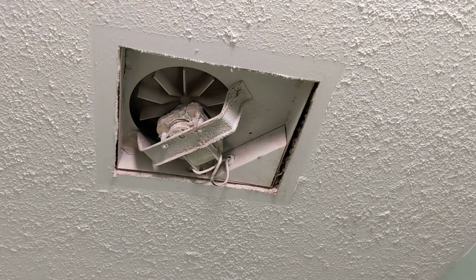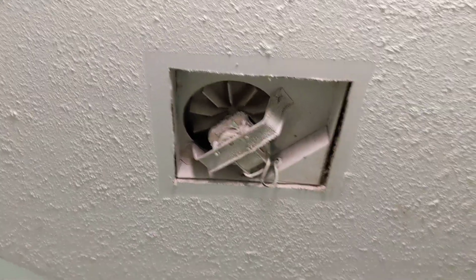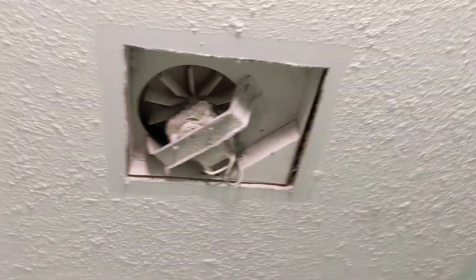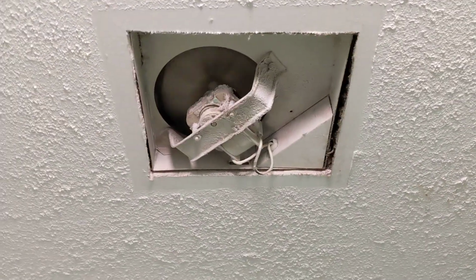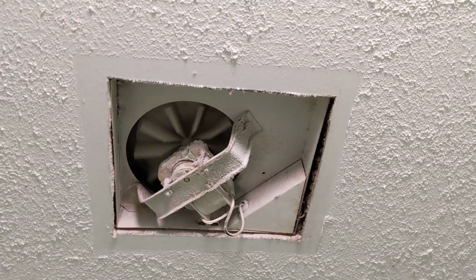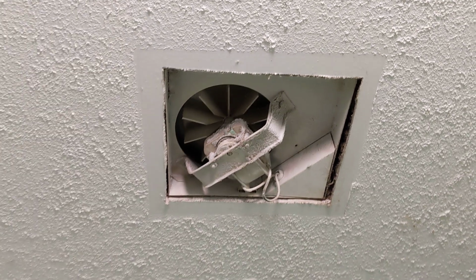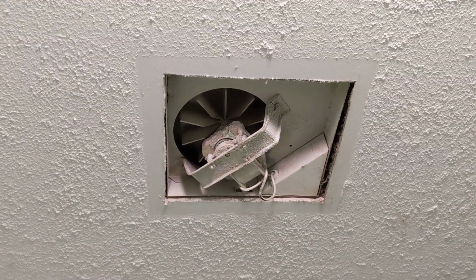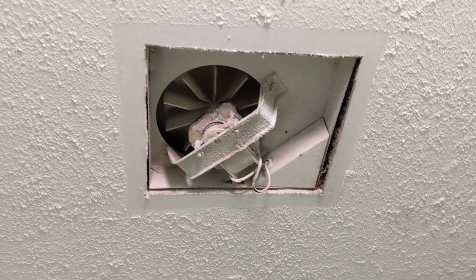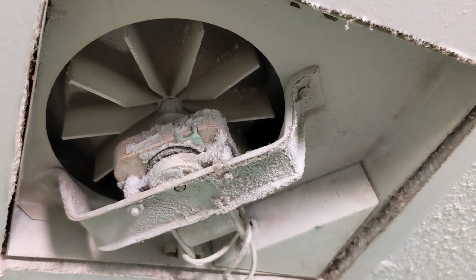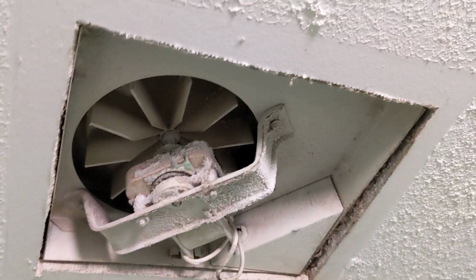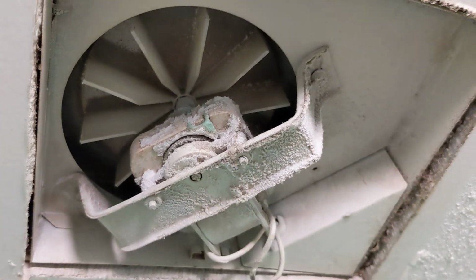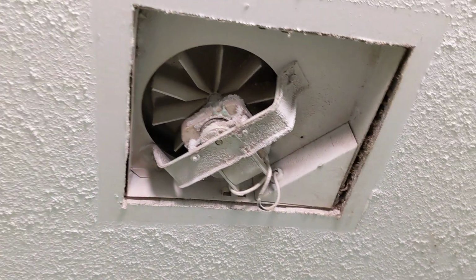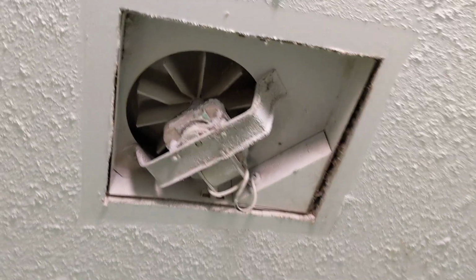So before we went upstairs, I did want to note something. This is in a bathroom, so this is a typical bathroom exhaust fan. So we turn the fan on, it turns on, pulls that high relative humidity air up through the fan, through the exhaust ductwork, and then usually out through the roof, or sometimes just into the attic. And then the attic has ventilation, soffit vents, steeple vents, ridge vents, things like that to discharge that high relative humidity.